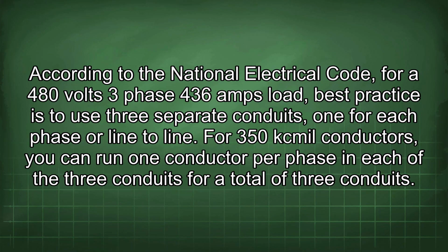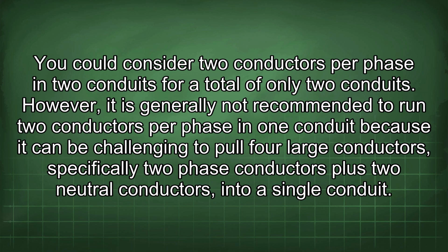According to the National Electrical Code, for a 480 volts 3-phase 436 amps load, best practice is to use 3 separate conduits, one for each phase or line to line. For 350 kcmil conductors, you can run 1 conductor per phase in each of the 3 conduits for a total of 3 conduits. You could consider 2 conductors per phase and 2 conduits for a total of only 2 conduits.